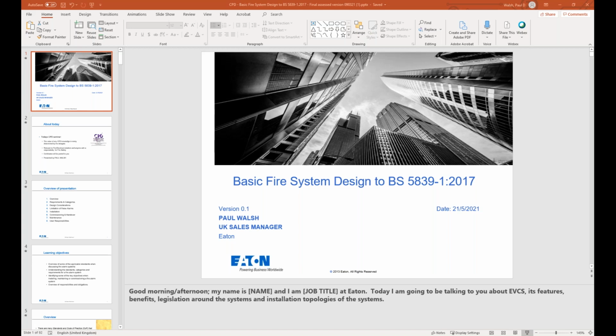In clause 6, again just before an order is placed, the responsibility for each of the following, system design, installation, and commissioning, should be documented. As I said earlier, that's quite critical. There should be a certification process, and there are a number of different variants to that. So there isn't one standard rule. You can have a different certificate under the NSI certification as to the BAFE certification.